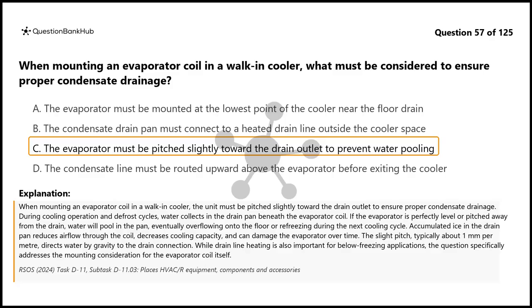Accumulated ice in the drain pan reduces airflow through the coil, decreases cooling capacity, and can damage the evaporator over time. The slight pitch, typically about 1 mm per meter, directs water by gravity to the drain connection. While drain line heating is also important for below freezing applications, the question specifically addresses the mounting consideration for the evaporator coil itself.